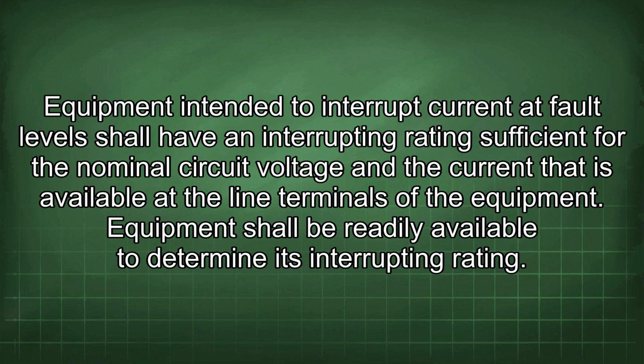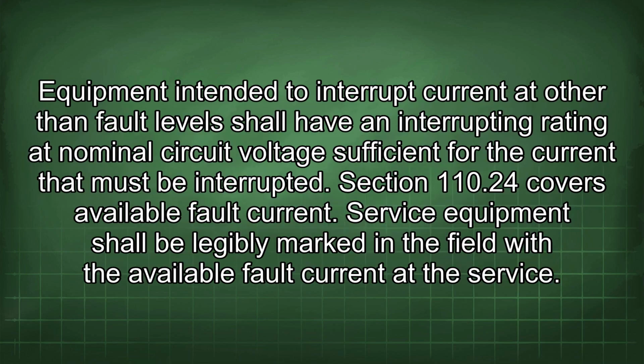Equipment intended to interrupt current at fault level shall have an interrupting rating sufficient for the nominal circuit voltage and the current that is available at the line terminals of the equipment. Equipment shall be readily available to determine its interrupting rating. Equipment intended to interrupt current at other than fault level shall have an interrupting rating at nominal circuit voltage sufficient for the current that must be interrupted.